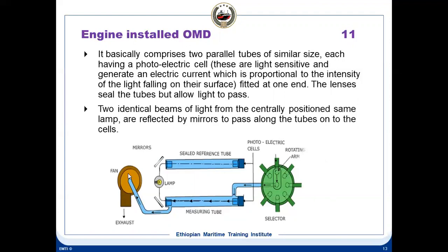The concentration you can check on this, because if there is actual oil mist, you'll see it on this. You must have seen on the generator itself, on the outside, they have an LED screen. The LED bar will go up and down. Whenever the concentration goes high, the LED bar light will go up. That means the concentration is high. And the normal fault with this is only either the fan failure, or maybe a failure on this side.